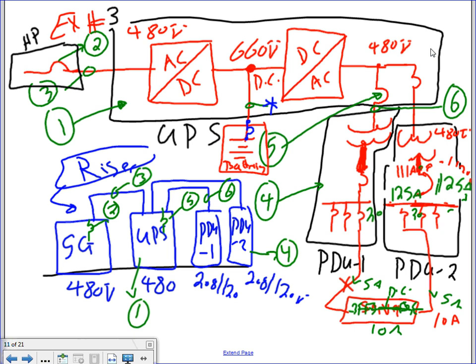Any comments, guys, about PDUs, UPSs? PDUs, UPSs. This is the key word here. So shall we go size these, how many things? Six things for this system? Your job, guys, is to size the UPS and size all the associated feeders and overcurrent protection devices for it.